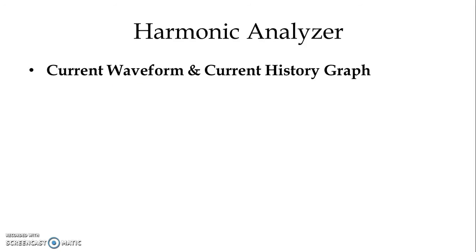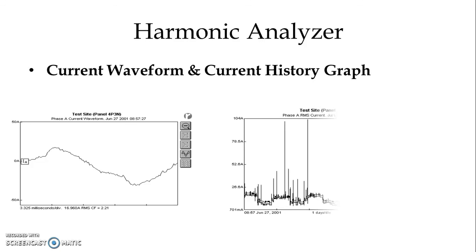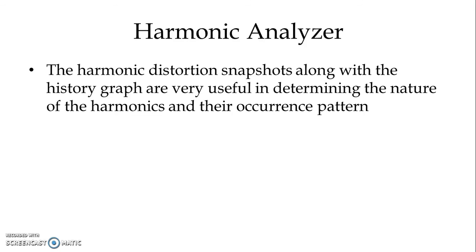We can have a current waveform as well as a current history graph. In the figure we can see one current waveform of a lighting panel which provides supply to fluorescent lights, and at the same time we can have a current history graph. The harmonic distortion snapshots along with the historic graph are very useful in determining the nature of the harmonics and their occurrence pattern.